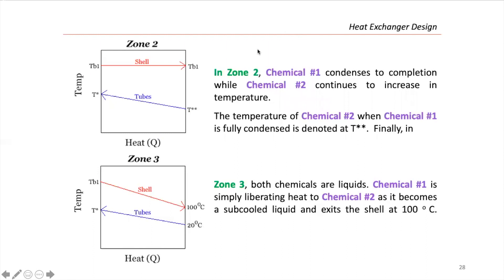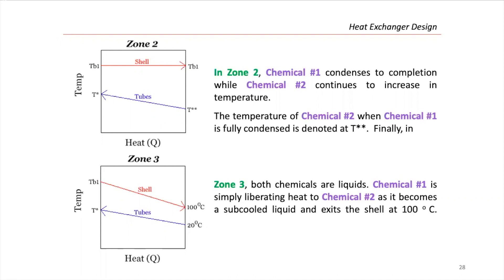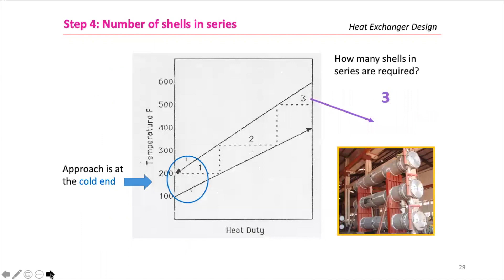In zone two, chemical one condenses to completion while chemical two continues to increase in temperature. The temperature of chemical two when chemical one is fully condensed is denoted T**. Finally, in zone three, both chemicals are liquid — chemical one simply liberates heat to chemical two as it becomes a sub-cooled liquid and exits the shell at 100°C. Once we establish our zones and thermal diagram, we solve like a regular heat exchanger but in pieces, using delta T1, delta T2, and the log mean temperature difference.